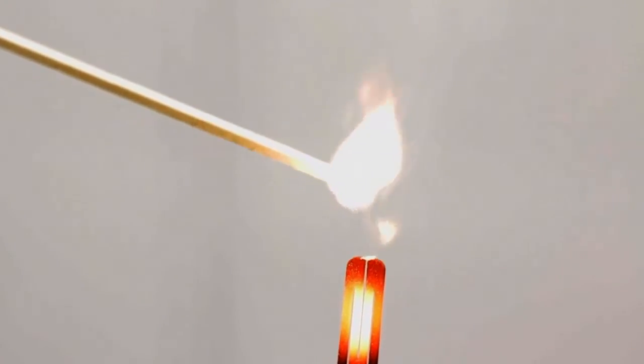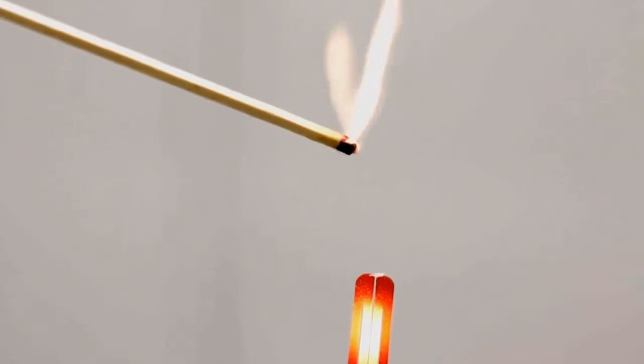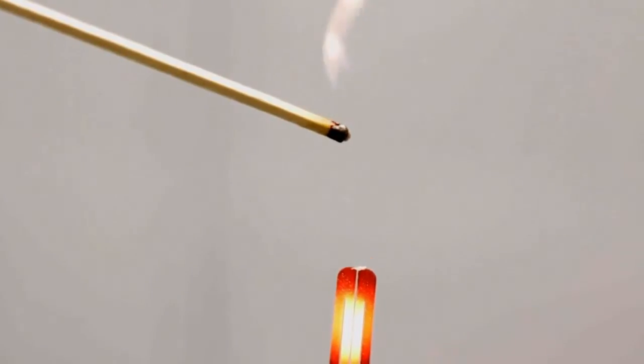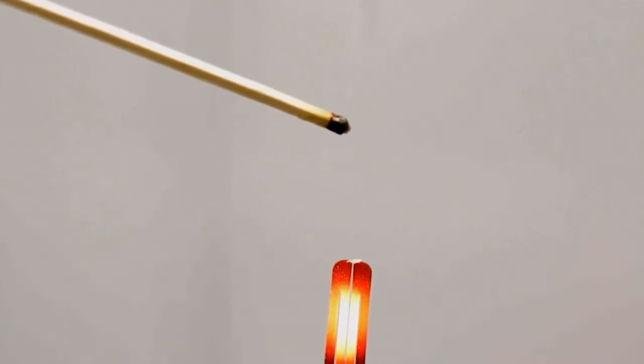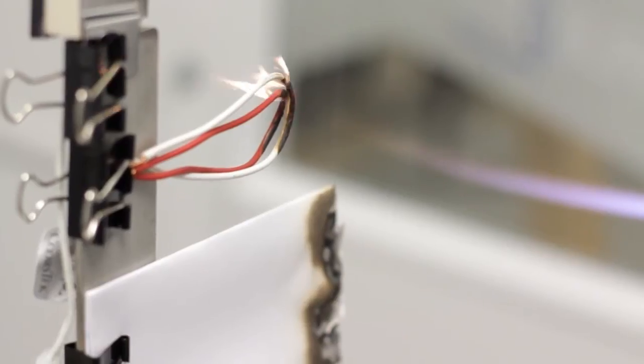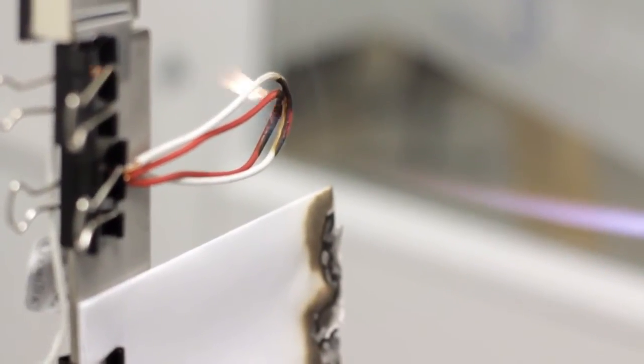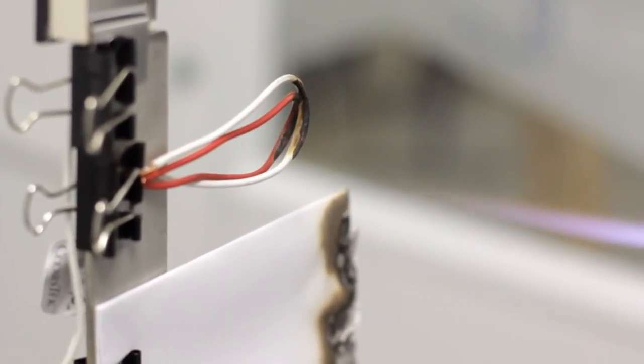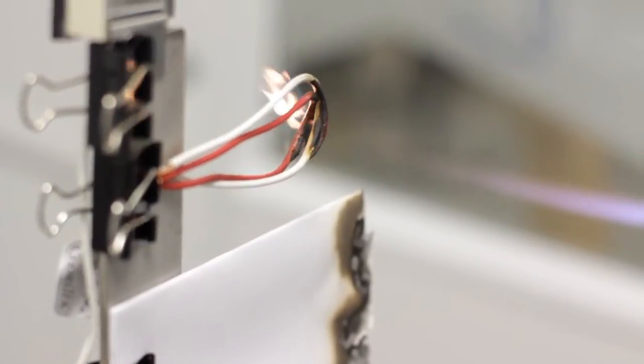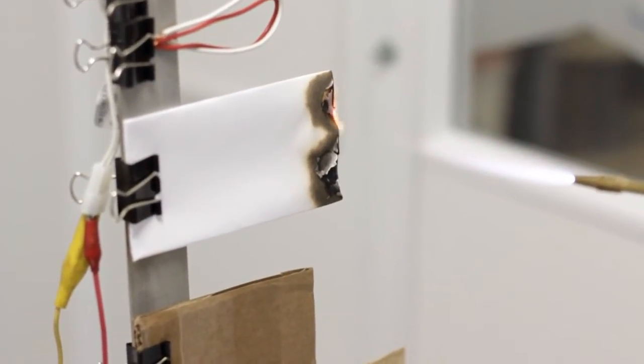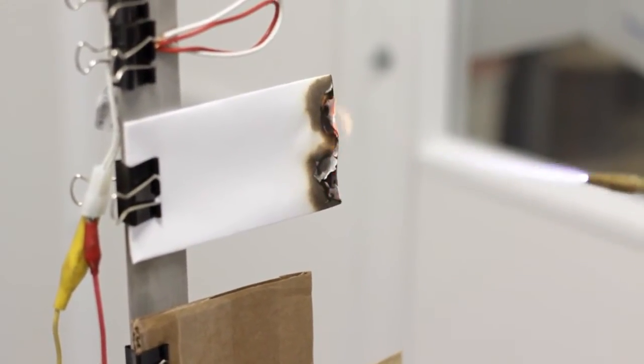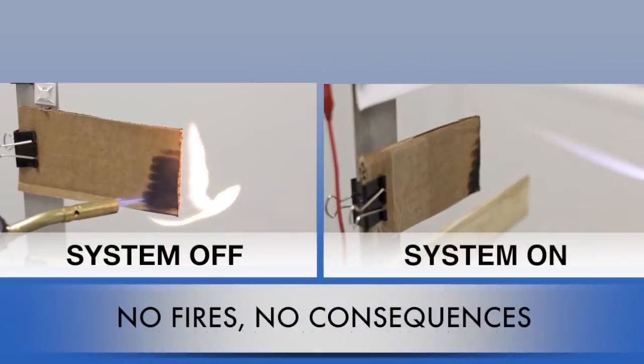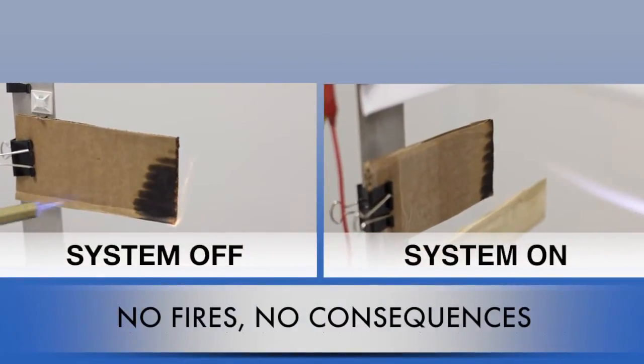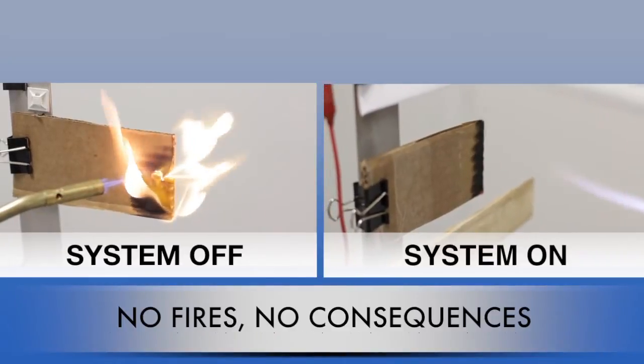What you see now is lighting a match in the controlled space with the oxygen level lowered. The match has some oxygen in the head, so once that oxygen is gone, there is no fire. Here is a flame being placed on a copper wire with a plastic coating, and you'll see that a fire cannot start. A piece of paper with the flame from the torch being placed on it, and the fire cannot be sustained. Now the same flame is placed on cardboard with the same result.